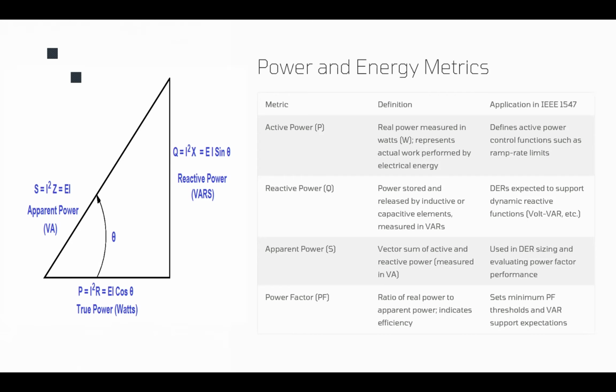Now, it could vary between 0 and 1. The power factor range is 0 to 1. 1 means we have purely active power, and 0 means we have purely reactive power. 1 and 0 would not happen in the real world, okay? But they are the ideal top boundary and low boundary of the power factor. Now, IEEE 1547 defines a certain limit that the DERs should work within regarding the power factor. For example, it's 0.9. They should not let the power factor go lower than 0.9. It could be lagging or leading, regarding the reactive power portion, but the power factor should remain higher than 0.9 based on this standard, IEEE 1547.